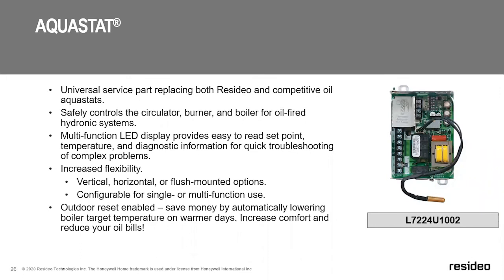It also has the ability to be outdoor reset enabled. Using our Aqua Reset system, which is compatible with this AQUASTAT, you can actually convert this into an AQUASTAT that will react to outdoor reset conditions, enabling fuel efficiency for the customer. By having outdoor reset, you could have a savings of up to 15% on your fuel bills, because it's going to react to how hot or cold it is outside, because it looks at your outdoor temperature, and then it'll run the burner according to the needs of the system.